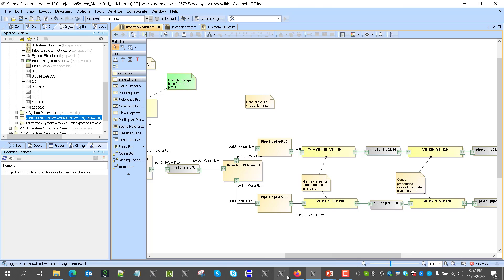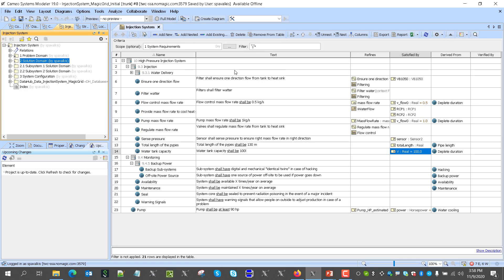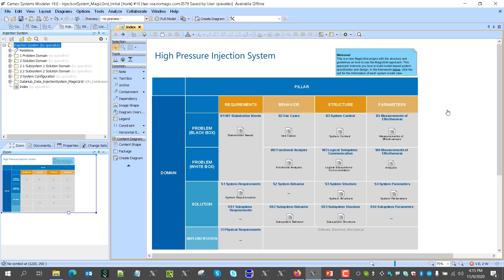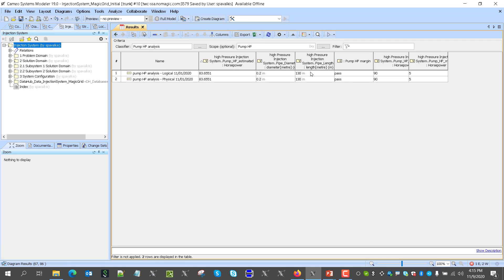Now let's go and implement the next change. The next change comes from the distance of the pipes. We go to the requirements here and get a new version of requirements. We'll check the impact and analyze suspect links to show suspicious links. I see there is a total length of the pipes requirement impact. Now we will check the impact of this requirement change on the logical architecture. Here we see analysis for pump power based on the length of the pipes. Based on the previous length of 130, we see this was the required pump with a 5% margin — total 90 horsepower.